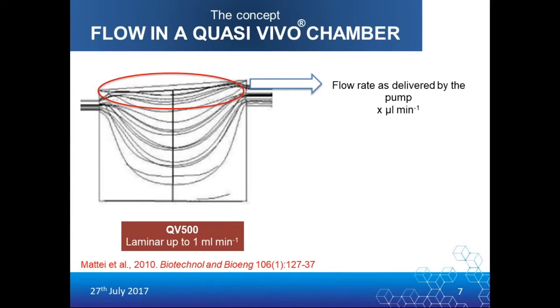And here's a diagram of the Quasi Vivo chamber. So this is the Quasi Vivo 500. When it was designed, there were extensive computer models done on the system to ensure that the flow was adequate and the oxygen conditions at the base of the chamber were adequate to allow cells to thrive. So here you can see on the left-hand side is the inlet, and the right-hand side we have the outlet. There are two things that you might notice from this diagram. The first is that the inlet is both lower and narrower than the outlet. And the second thing is that the roof itself is sloped towards the direction of the outlet. This is to ensure that we don't get any bubbles within our system. And if we do get bubbles, they're quickly shepherded from the inlet towards the outlet.